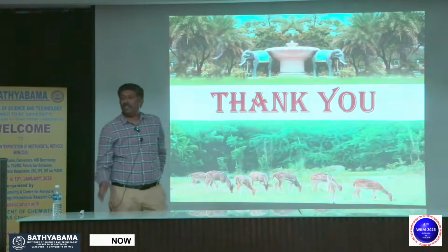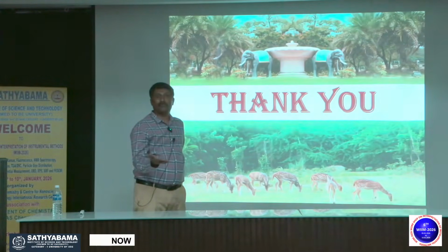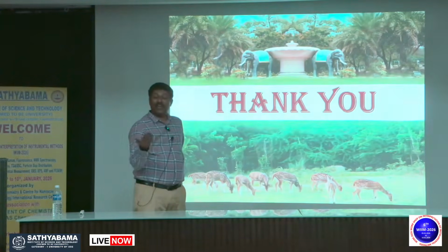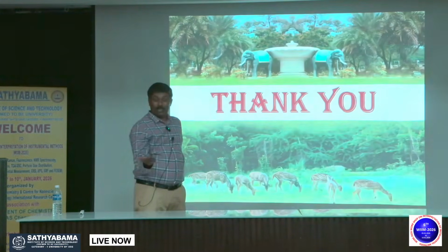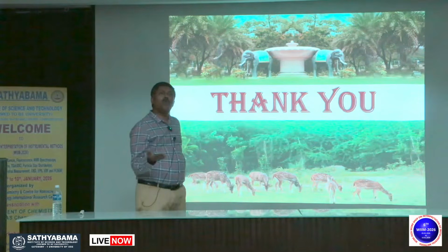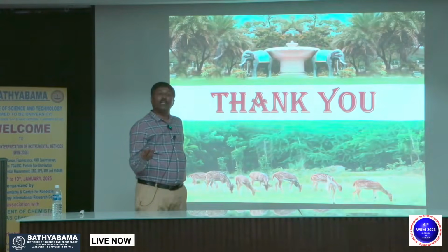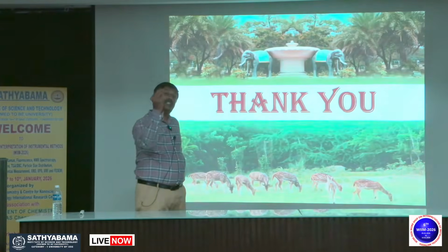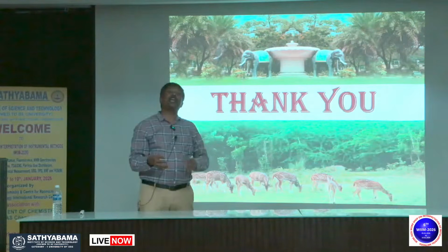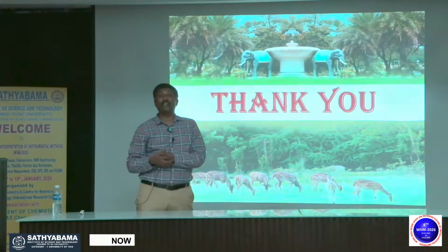Yes, because most of the weight loss is in a gaseous form. Because if it is decomposed, it will not remain in the balance. So what kind of gases are mostly there? It is H2O, CO2 or other kinds of low molecular weight gases. So if we know how much of this comes in addition to our carrier gas, that also can be quantified or characterized. That's what I told. Evolved gas analysis.